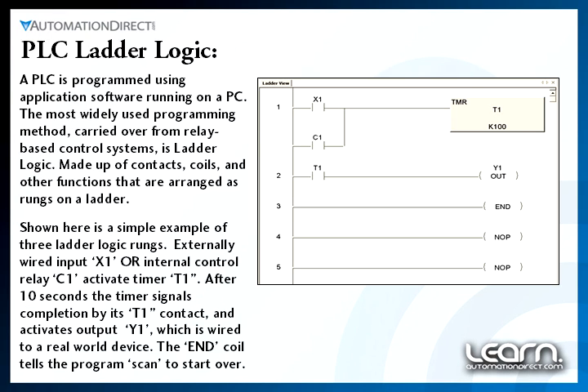How are PLCs programmed? In most cases, application software running on a personal computer is used to create the PLC's decision-making logic. Although other programming methods exist, the most widely used is still ladder logic, which is a carryover from relay-based control systems. Ladder logic consists of contacts, coils, and other functions arranged on rungs, not unlike the rungs on a ladder. In the simple example shown here, a timer is activated by either an external device wired to input X1 or an internal control relay labeled C1 — notice the logic OR in the example. After a preset amount of time of 10 seconds, the timer signals completion by closing its T1 contact and activating output Y1, which controls a real-world device wired to the PLC's output terminals. An end-coil is shown in the last rung to tell the program to go back to the start and check the rungs in order again.